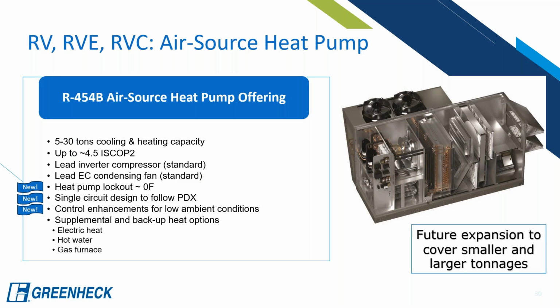So all of these are available with that air source heat pump I was telling you about. In fact, it's been available for a while, but now we have the new refrigerant that I was just talking about available with it. As of August, we'll be able to start selling it this way. The R454B air source heat pump available up to 30 tons of cooling, like I said. Lead inverter compressor standard, EC condensing fans are standard. It has the new heat pump lockout of 0 degrees, which we'll get into what the logic means on that. Single circuit design, which follows our packaged DX line, and some control enhancements for low ambient conditions. And we'll also always be able to provide electric heat, hot water, and gas furnace as a supplemental or backup heat option.